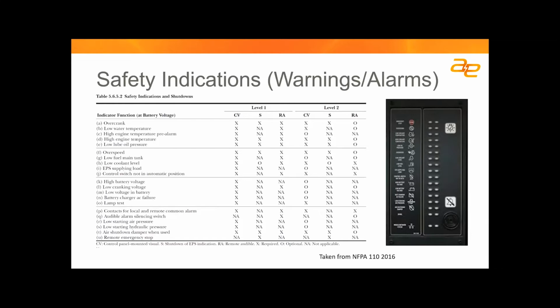For Level 1, you can see the types of alarms. CV means control panel mounted visual, and quite a few fall into that category. The S means that particular alarm is designated as a shutdown alarm, meaning the generator should shut down if it occurs. The RA means that alarm needs to be remotely audible — some type of siren or something that brings attention to the fact that an alarm is present.